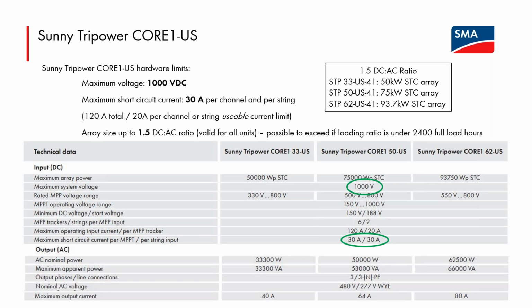You have to stay under 1,000 volts DC for open circuit voltage. And the second value circled is a short circuit current limit. And the data sheet shows it as per maximum power point tracking channel and per string input. And that short circuit current limit is the same for each channel, which has 2 string inputs, as well as each string input on the inverter.